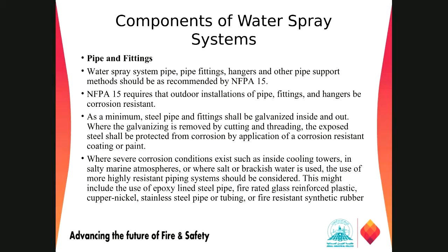Now, normally with outside installation of metallic pipe, there are more chances of corrosion inside those pipes, because we don't have water inside the piping most of the time. Water goes inside only when there is an actual fire, right? So due to that, air will always be present inside the piping, and that will cause the piping to corrode faster than recommended. Those corrosions will damage the piping. This is why NFPA 15 says that this kind of piping should be galvanized inside and out, right?